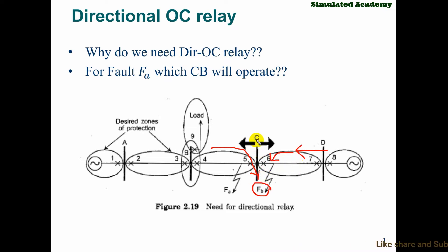If you want to find a reference: for fault at location between 5 and 6 — in 5 the current is towards the bus, and in 6 it is away from the bus. So who needs to operate? Circuit breaker 6 needs to operate.